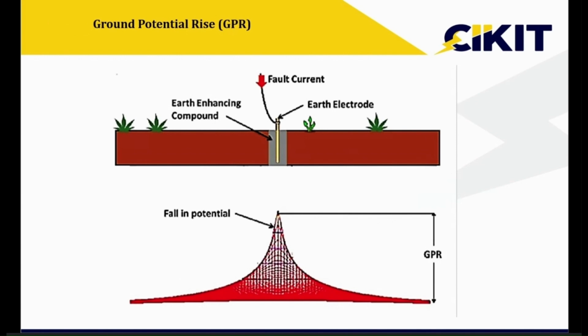Right. As I mentioned, during this discharge of current into the ground, the ground potential itself will increase. At normal conditions, we refer to the ground potential as zero voltage, but at the time of fault current discharge, the ground potential won't be at zero voltage, and it will increase to a greater value. And this voltage will drop suddenly as you move away from the earth electrode. Here you can observe that the potential is much higher very near the earth electrode, and as you move away from it, the potential keeps reducing. Somewhere away from the earth electrode, the potential is much lower. So there will be a huge potential difference between the points.